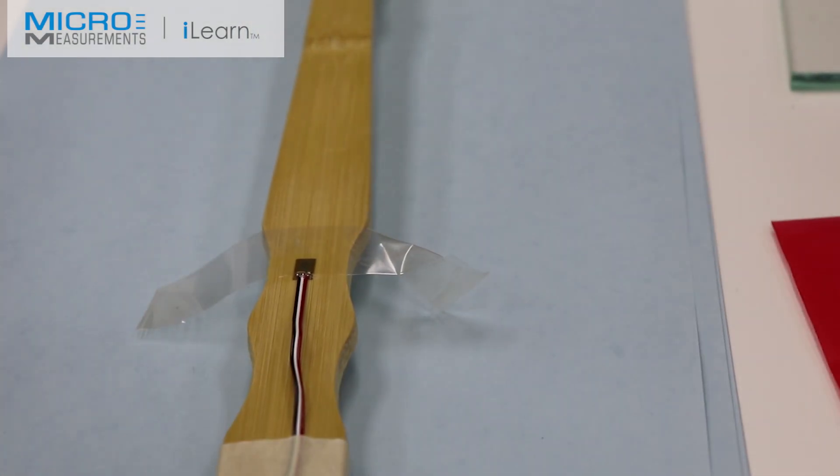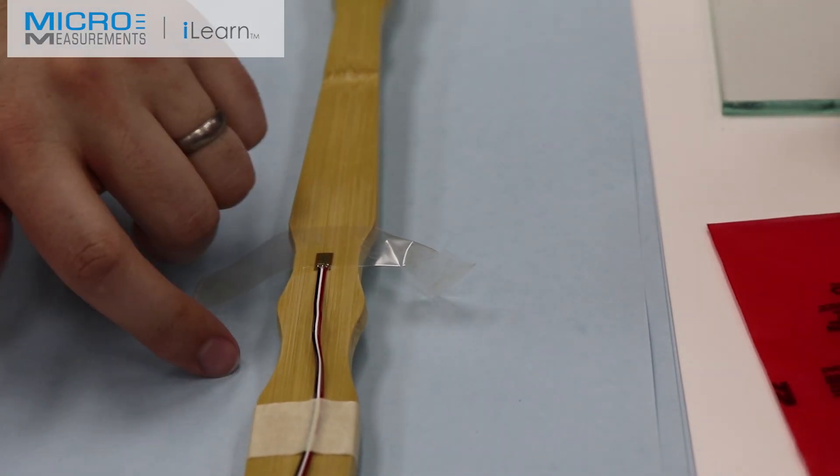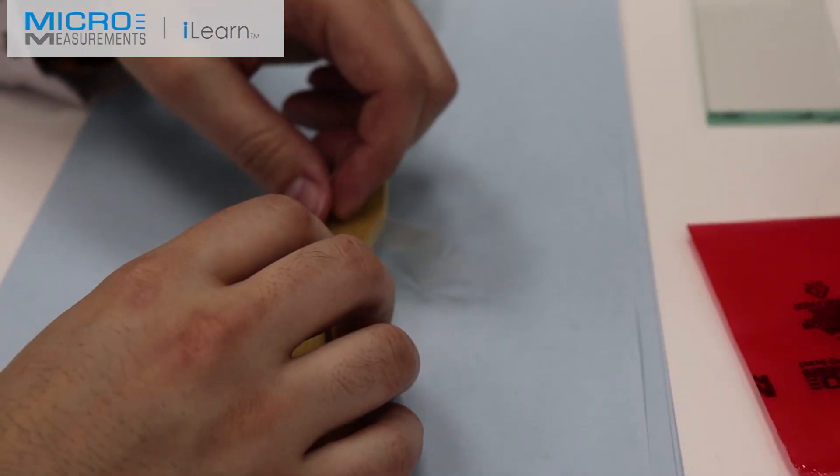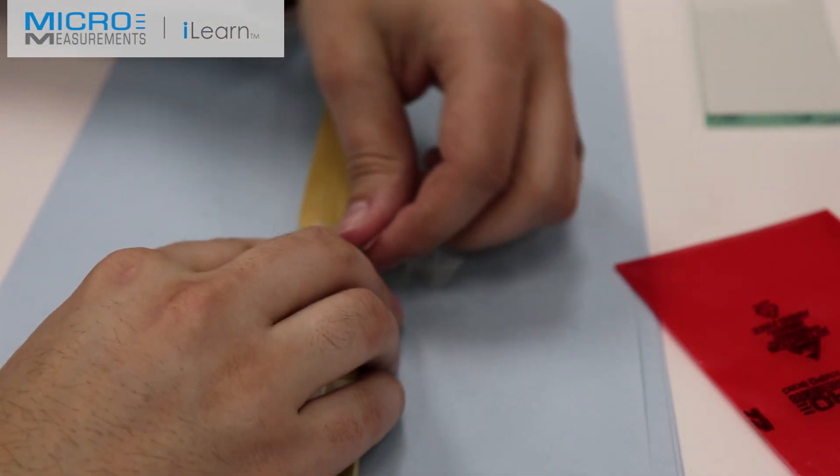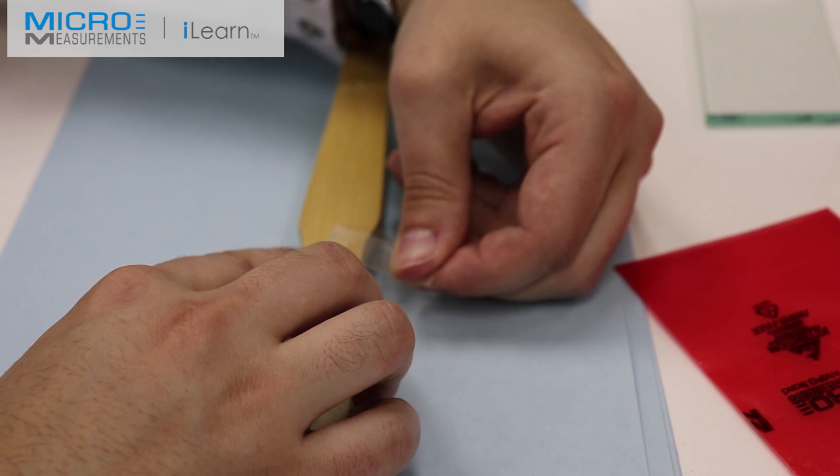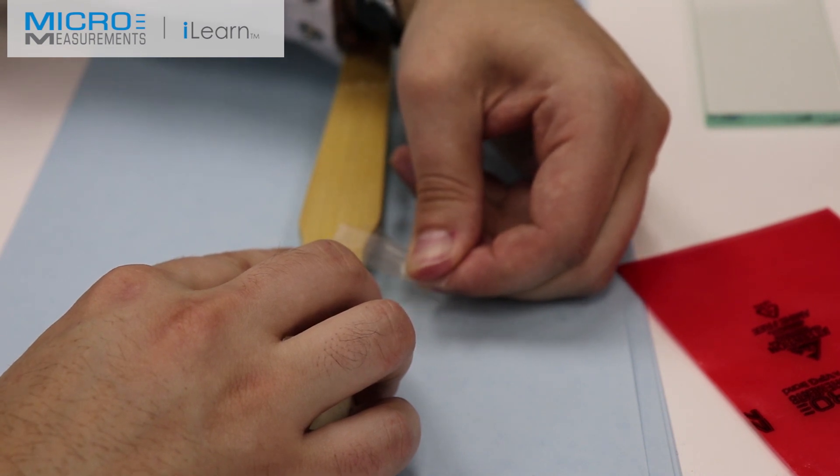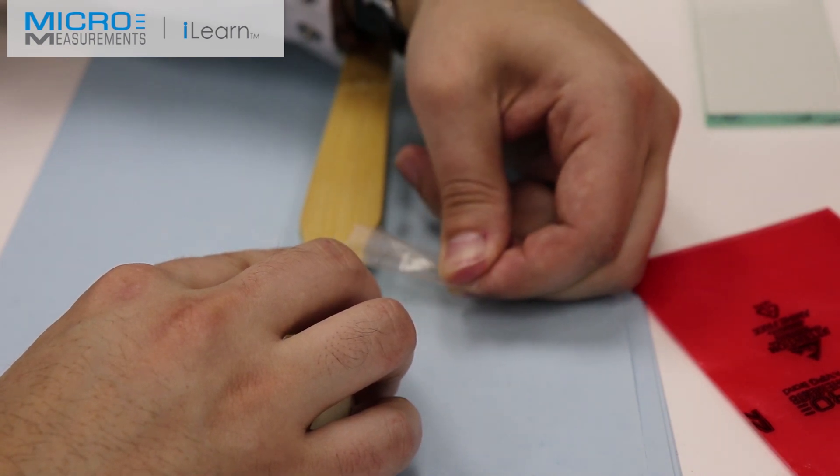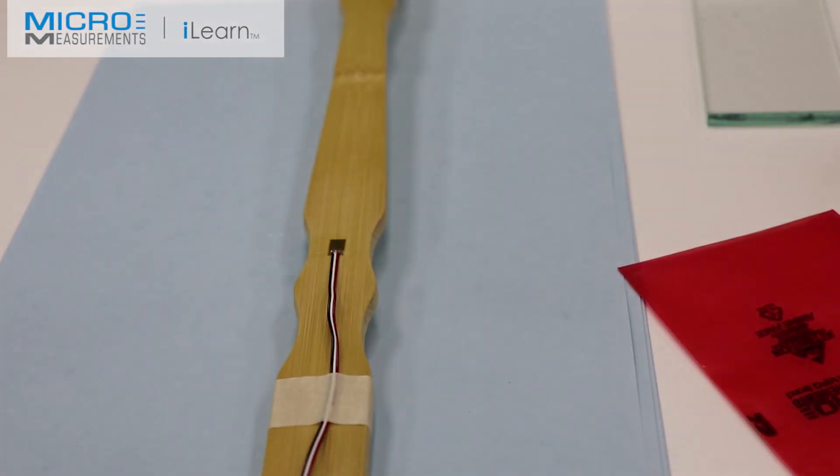He's going to, instead of lifting the tape at a shallow angle, now pull the tape 180 degrees back on itself. I would recommend putting your finger right down next to the gauge so the lead wire doesn't pull up. He's removed the gauge handling tape.